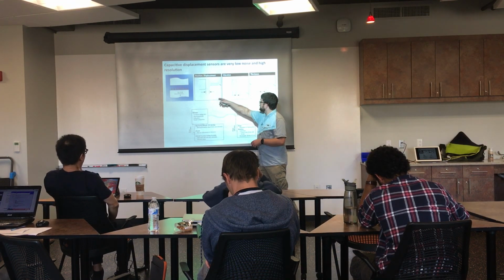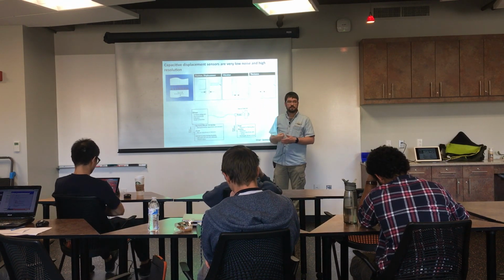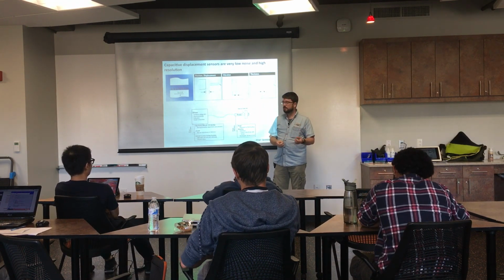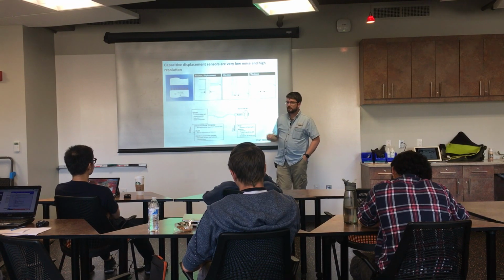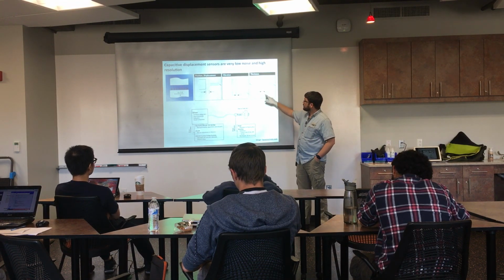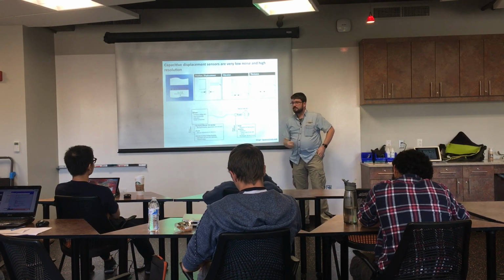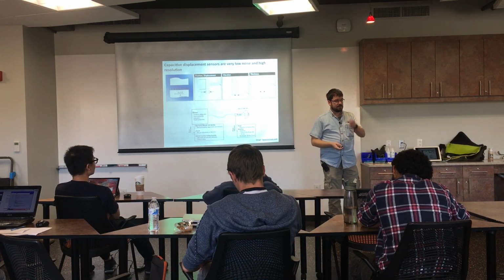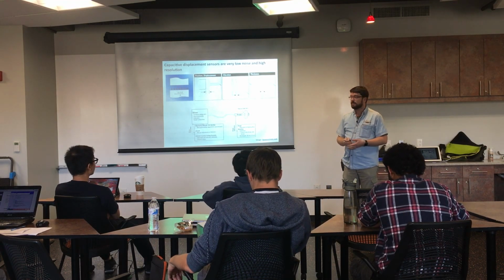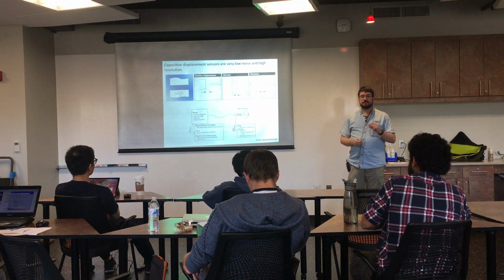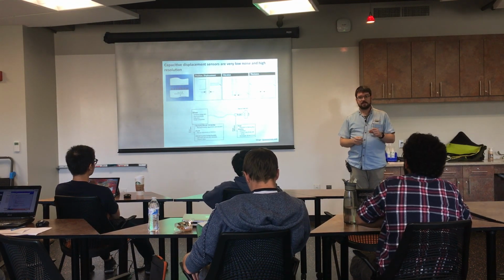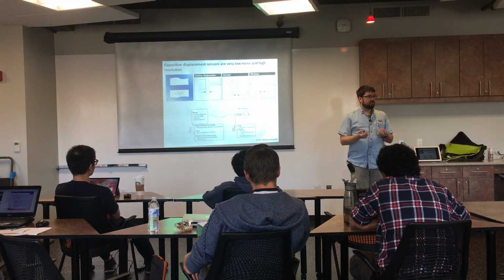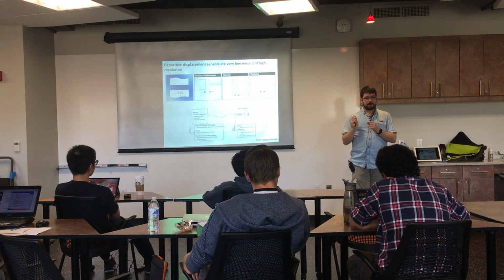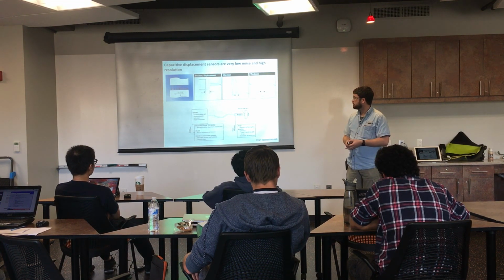So you can measure position. These have a very good high frequency response, up into the tens of kilohertz. So you can measure vibration if it's relatively low frequency. Or you can even use two of them, when they're manufacturing steel plates and that kind of thing, and pass it through and measure the thickness of an object. You can actually get absolute distance from these. With a DC-DT, it's pretty much relative, but these will give you absolute distance measurements if you reference it.